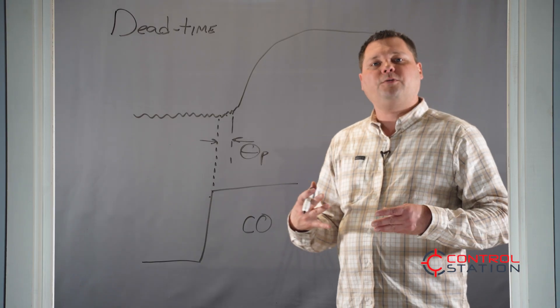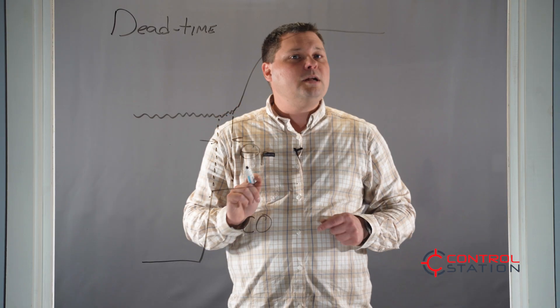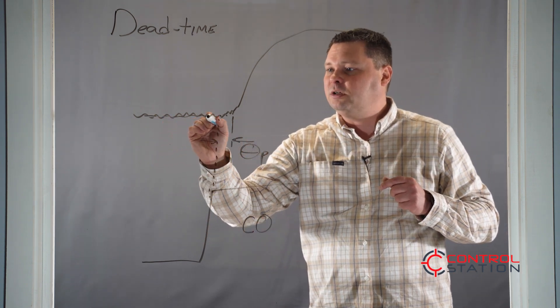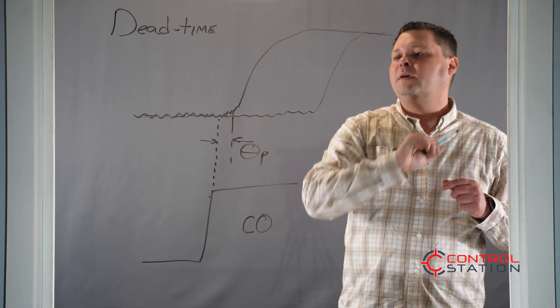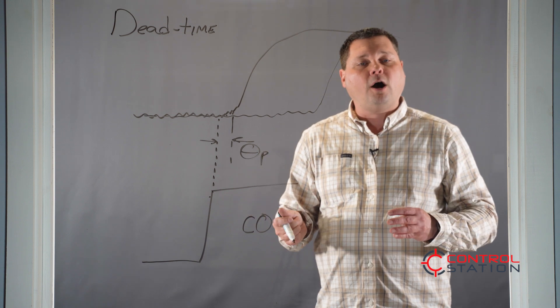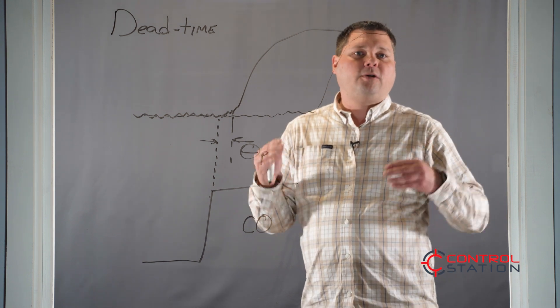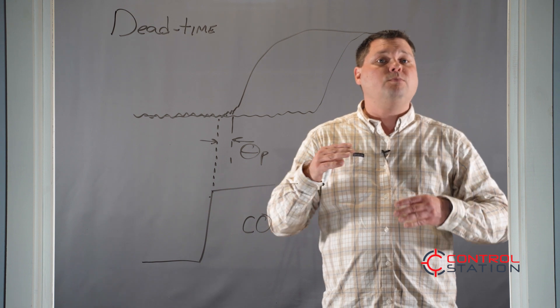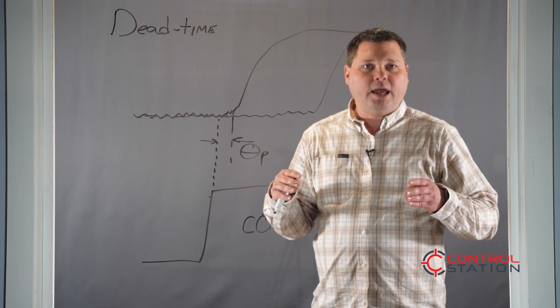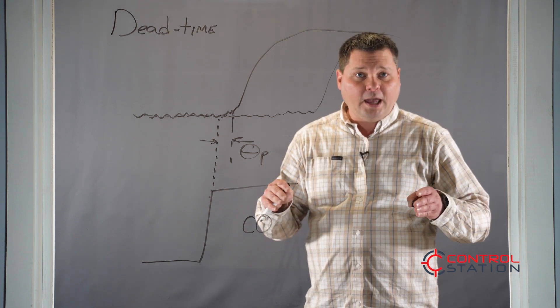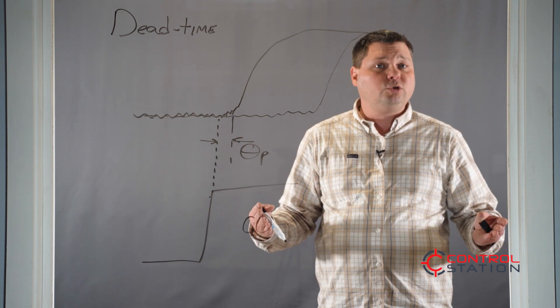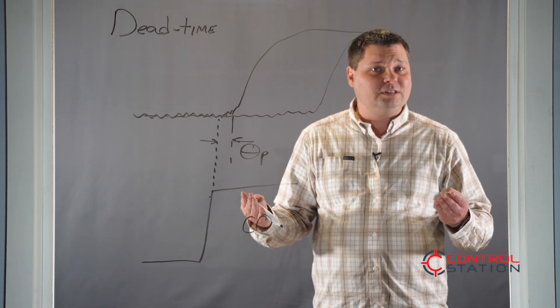Dead time is the killer of control. The larger this number is, that means there's more delay from the time you make a change till something actually starts to happen. Think about how difficult it would be to control the speed in your car — every time you move the gas pedal, it took five seconds for the speed to monitor any change. So you pushed it down and you wait, then you move. How annoying would that be? Well, your PID controllers have to deal with that all the time with your different systems.